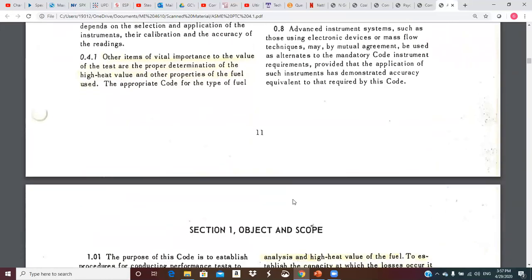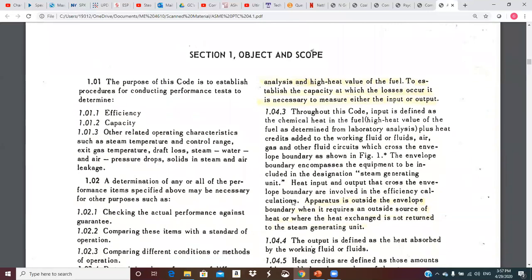The purpose of this code is to establish procedures for conducting performance tests to determine efficiency and capacity. So let's say you bought this $300 million boiler and your engineers didn't think it was operating as well, didn't have the efficiency, the capacity, or both. And you're anticipating trying to go back to the manufacturer and the contractor to do something about it. But how do you do a test?